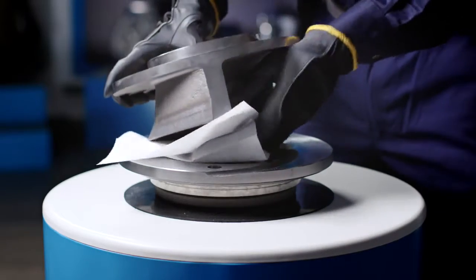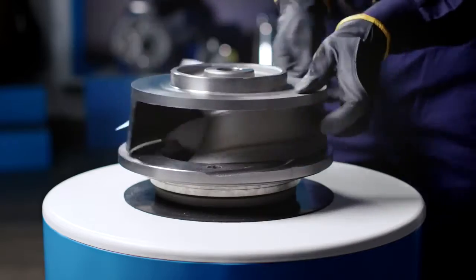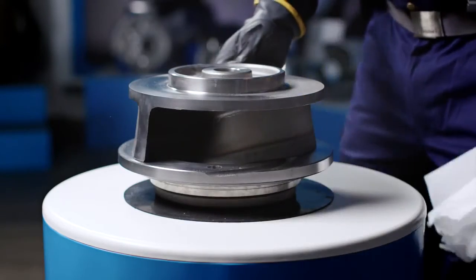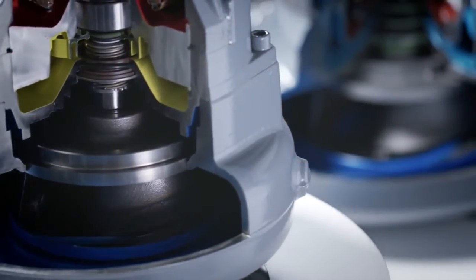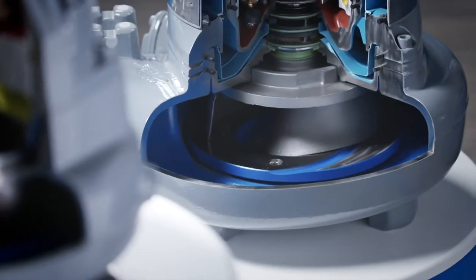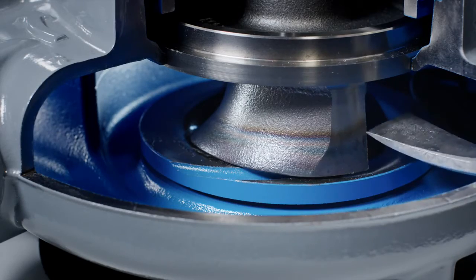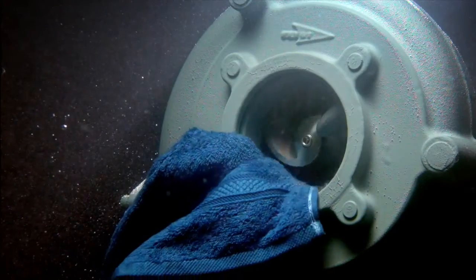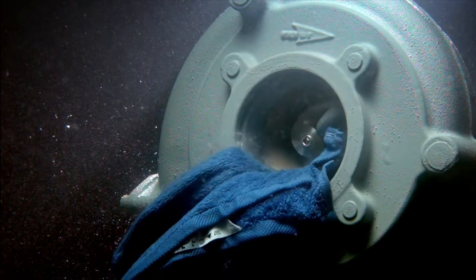This is how the N-Impeller Mechanical Self-Cleaning Technology works. After further development, the Adaptive N was launched for the smallest range of the N pumps. If a large object enters the pump, the impeller will move upwards and let it pass through. This N technology ensures sustained high operating efficiency of the pump.